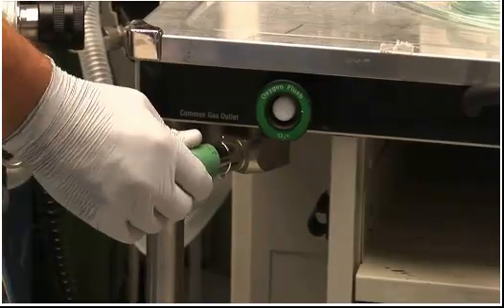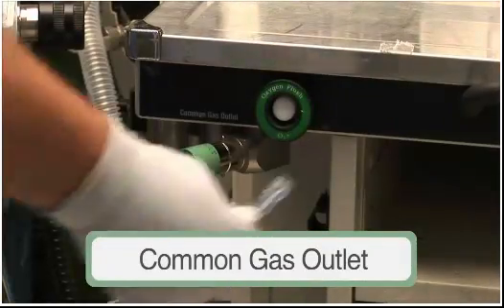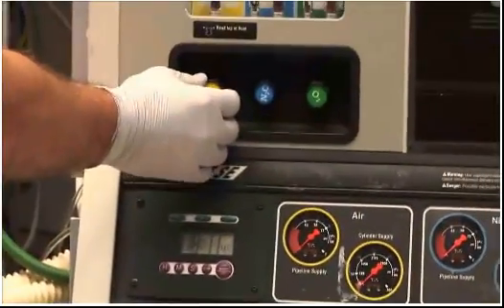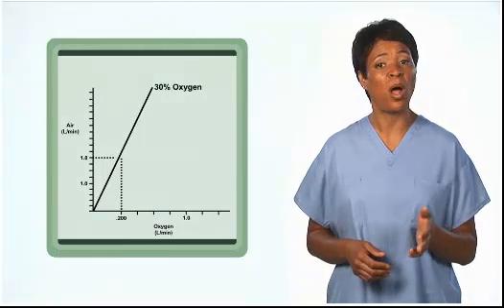Alternatively, use a three-gas anesthesia machine — one with air, oxygen, and nitrous oxide — that has a readily available common gas outlet, and take the blended gas directly from the outlet. Be careful about the ratio: it takes very little oxygen added to air to enrich the concentration beyond 30%. For example, adding only 200 milliliters per minute of oxygen to 1.8 liters of air creates an oxygen concentration of 29%. For three-gas anesthesia machines without an available common gas outlet, delivery of blended air and oxygen via the patient Y is possible.